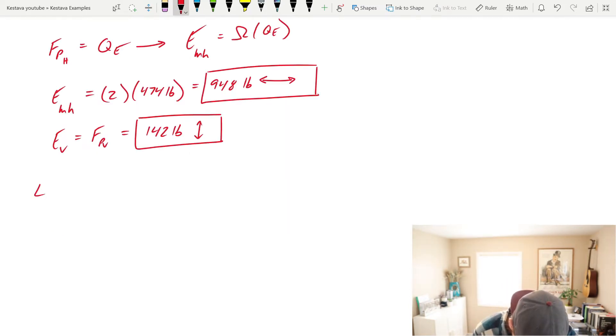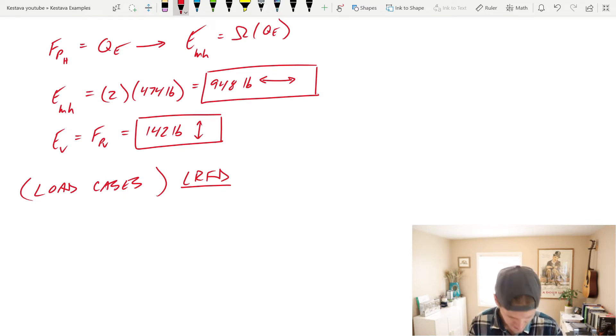We're still not done. Now we need to do load cases. Since we are anchoring into concrete, you know we're going to need to do LRFD design. I'm not going to flip us over, but you would check chapter two in order to get your load case that you would use. In our case, we're only going to check for one right now, but you would check for multiple. We're going to do load case seven as our worst case uplift condition.